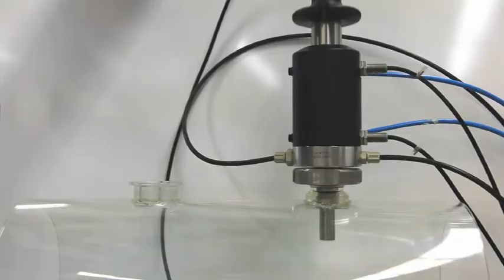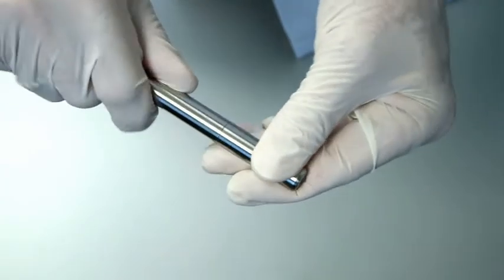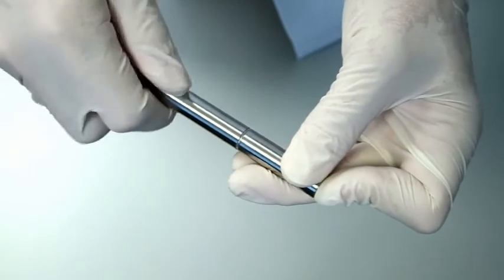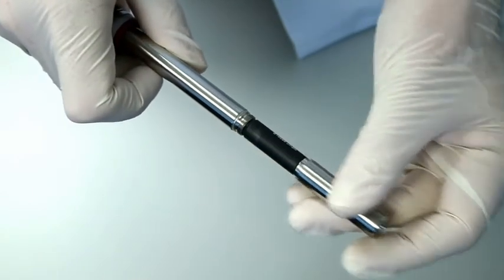After the sensor has been safely removed from the process, you unscrew the cap sleeve from the shaft and gently pull it off the sensor. Then you pull off the membrane body from the inner body. Be careful.